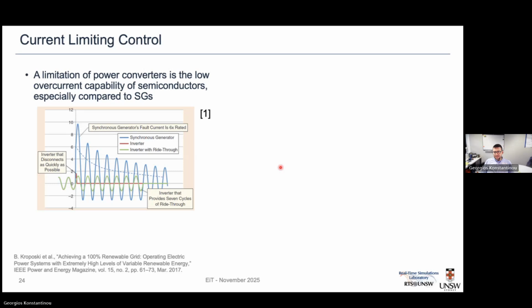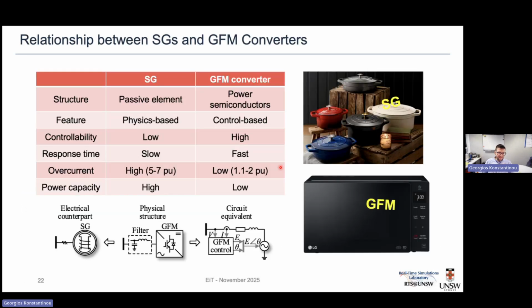And the extra complexity we need to work with is that our power electronic systems need to be current limited. One of the things I mentioned earlier is that they cannot handle high amounts of overcurrent going through them. So we need to limit this current, and this changes the way that they behave when they connect to the grid and when we have faults that we need to respond to.